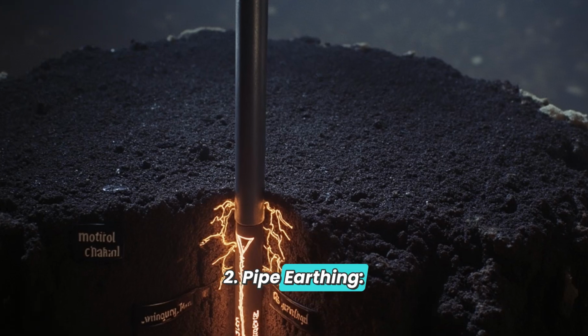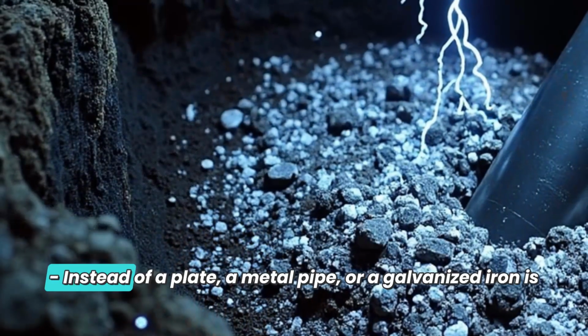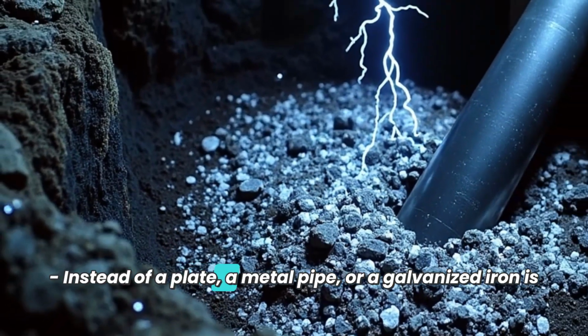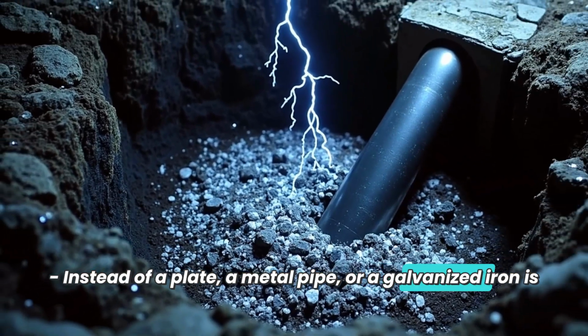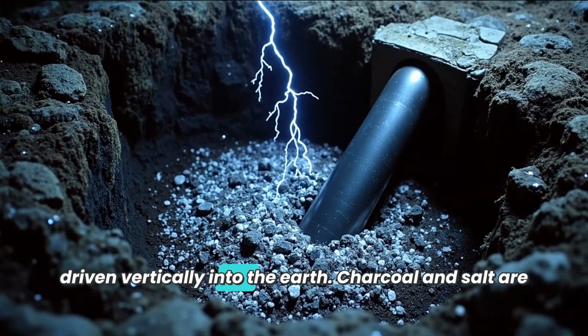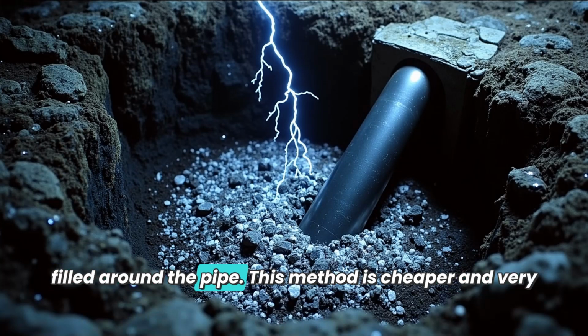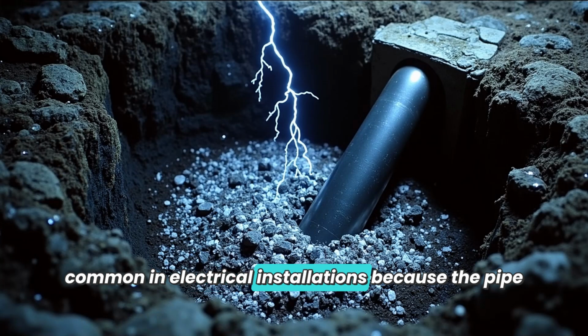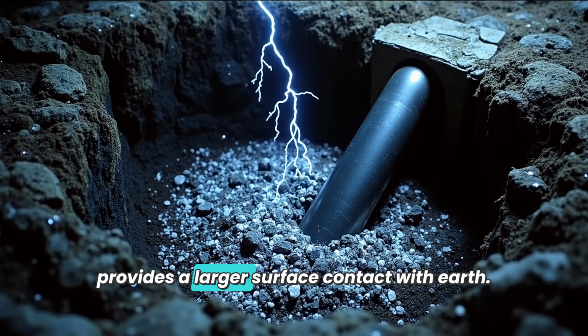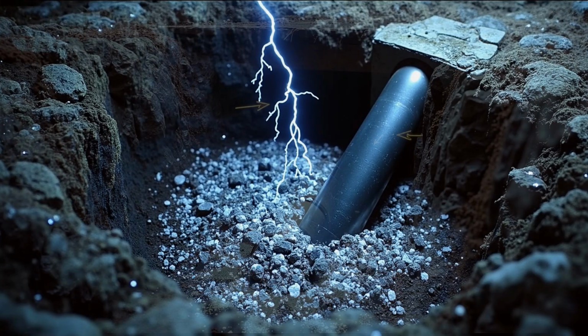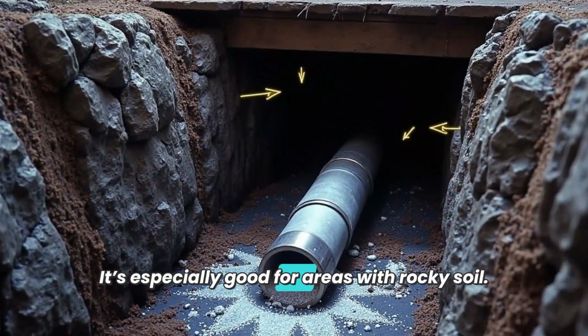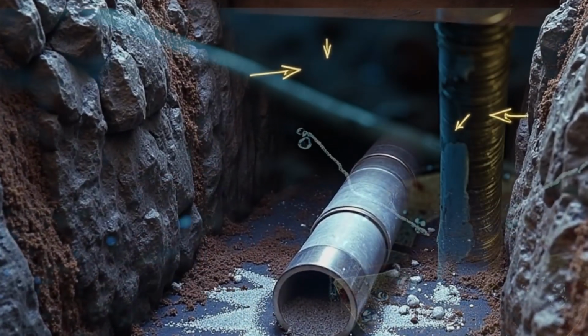2. Pipe earthing. Instead of a plate, a metal pipe of galvanized iron is driven vertically into the earth. Charcoal and salt are filled around the pipe. This method is cheaper and very common in electrical installations because the pipe provides a larger surface contact with earth. It's especially good for areas with rocky soil.